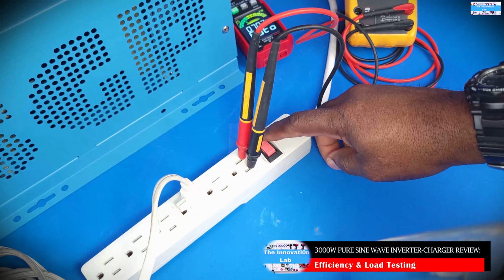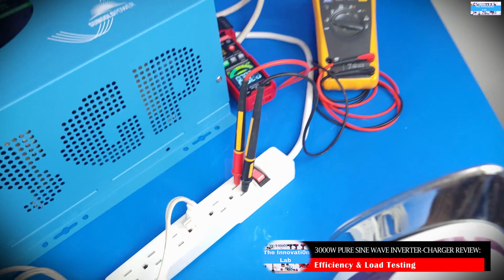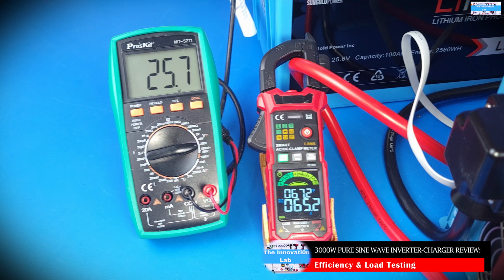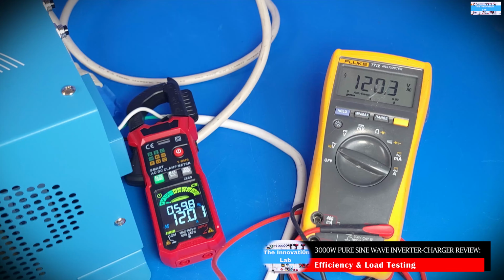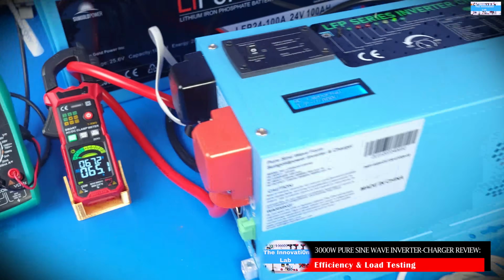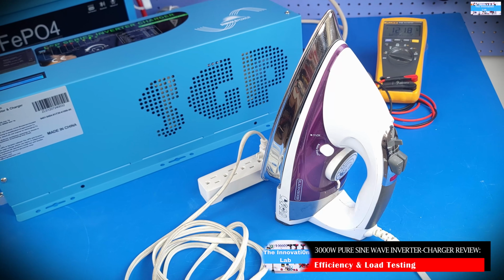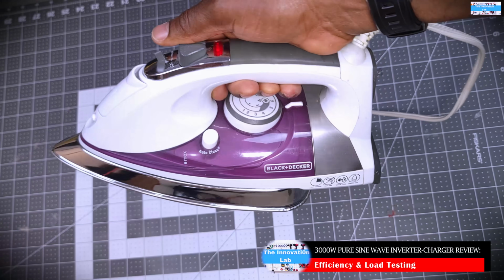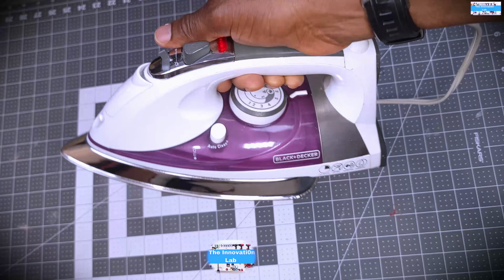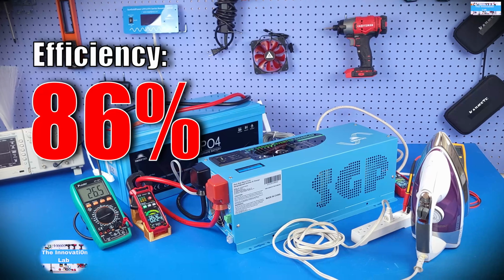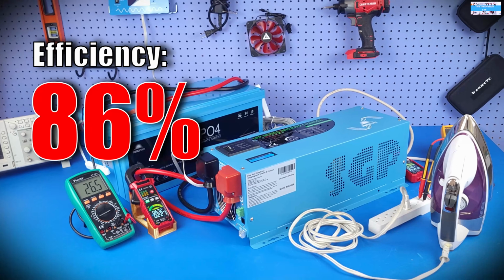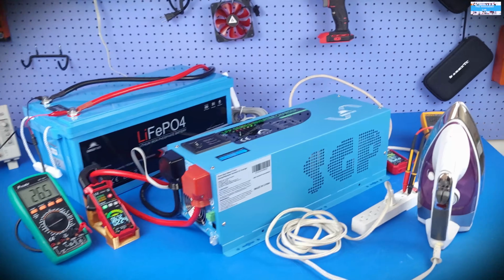Looking again at our DMM and current probes, we saw an input power from the battery system to the power inverter of about 1676 watts, and an output power into the electric iron of about 1440 watts, very close to 1500 watts. The electric iron is rated for 1500 watts, so it was pulling slightly less than that. Again, doing the math, this inverter gave us an efficiency of approximately 86%.